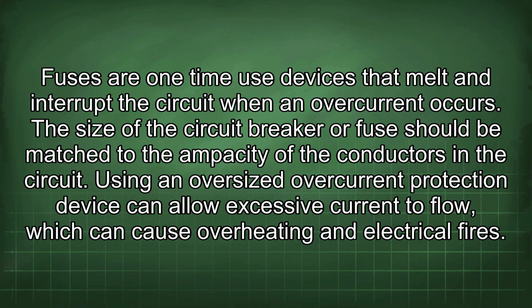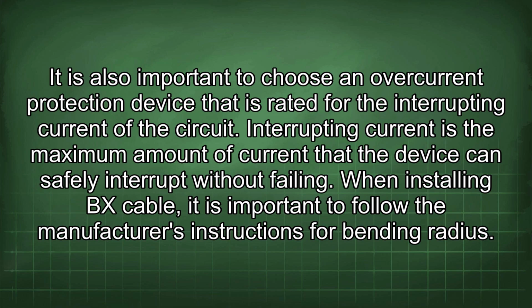The size of the circuit breaker or fuse should be matched to the ampacity of the conductors in the circuit. Using an oversized overcurrent protection device can allow excessive current to flow, which can cause overheating and electrical fires. It is also important to choose an overcurrent protection device that is rated for the interrupting current of the circuit. Interrupting current is the maximum amount of current that the device can safely interrupt without failing.